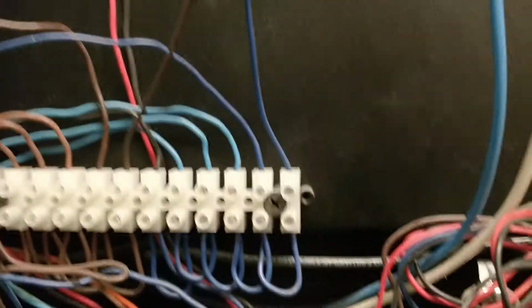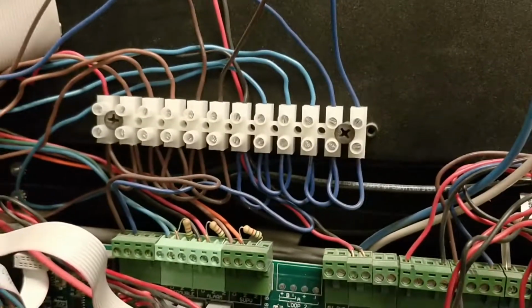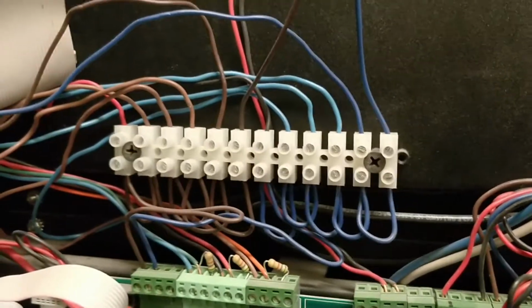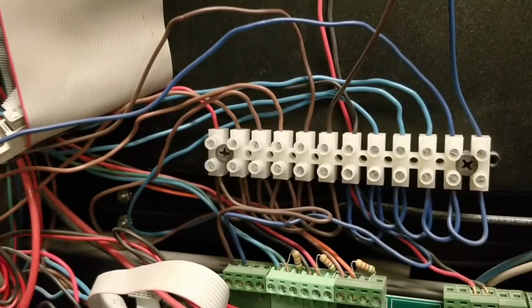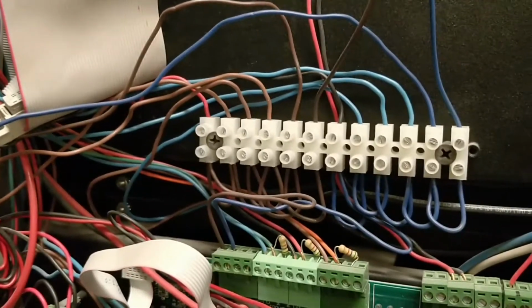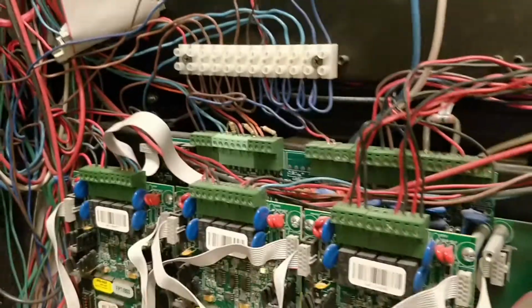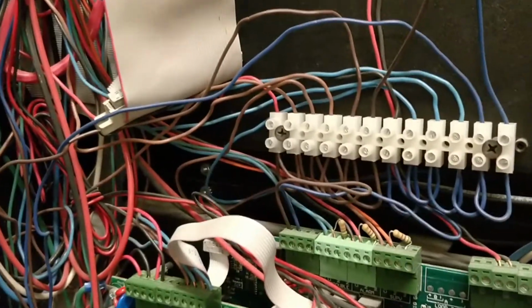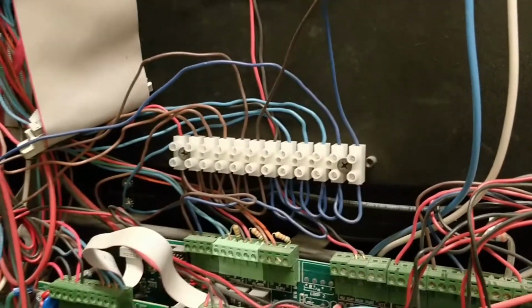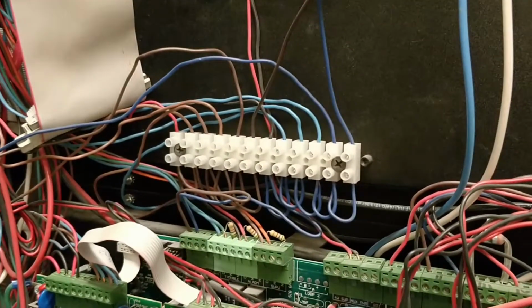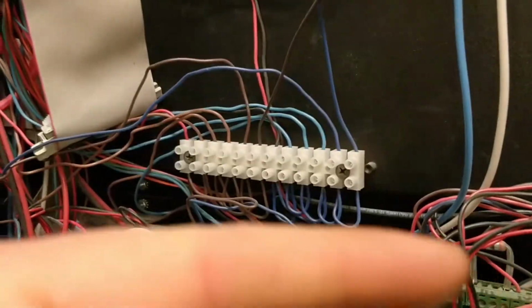And pretty sure, maybe I'll try and put a picture up, it's like the first page of the annunciators' installation instructions. It says right on it, no T-tapping or star wiring allowed for the RS-485, because each annunciator has an RS-485 in and out to the next annunciator.